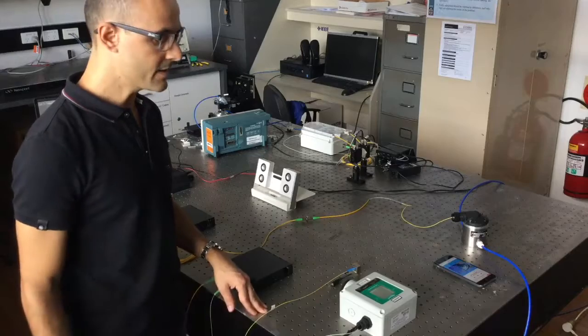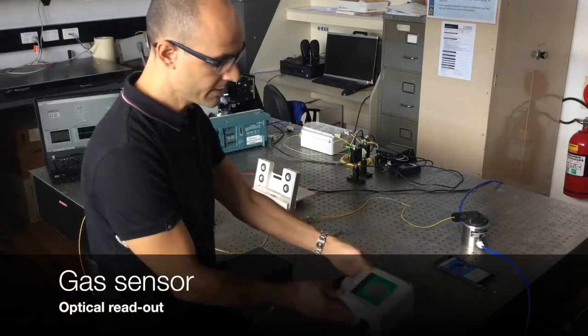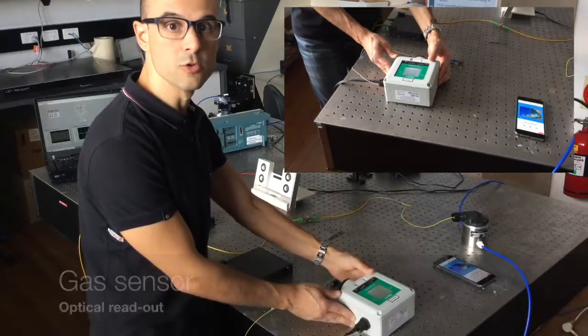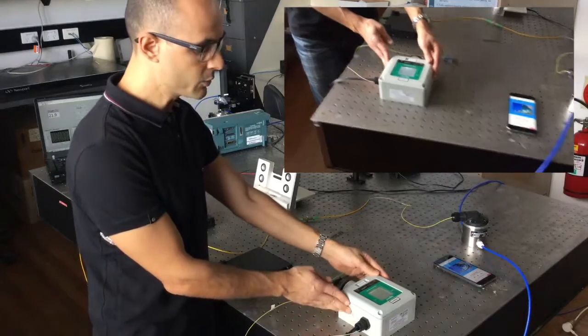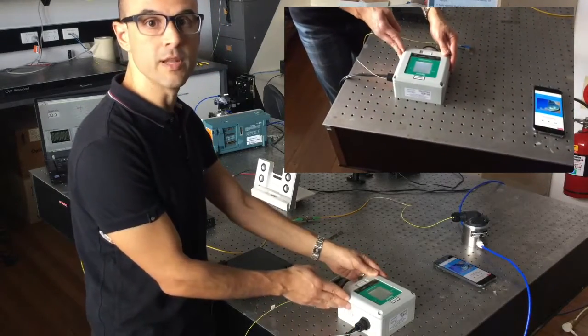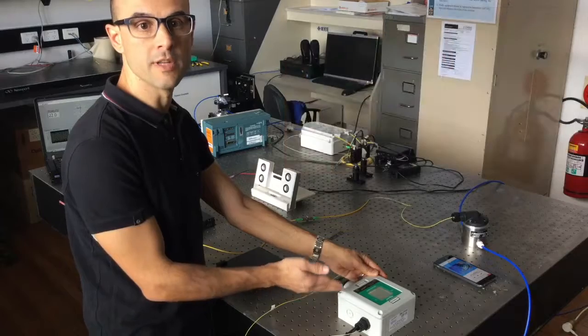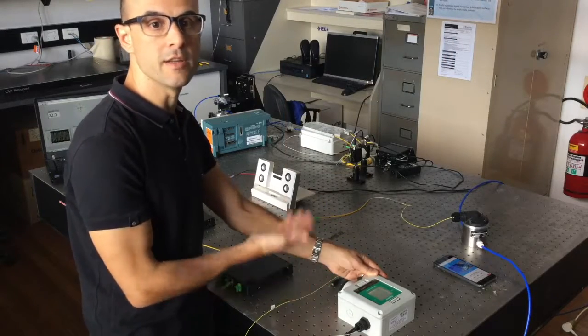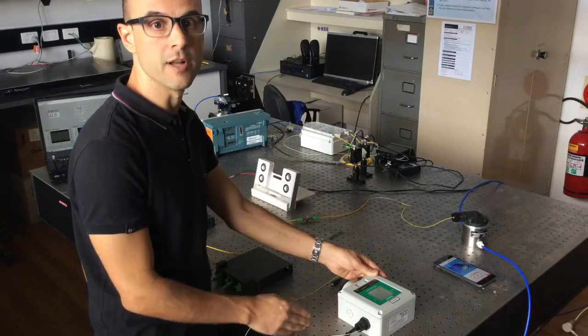Let's start with the gas sensor. Here we have retrofitted the standard gas sensor with a 4 to 20 milliampere output. What we did, we connected the 4 to 20 milliampere output to a voltage controlled oscillator in order to generate a square wave of a well-defined frequency.